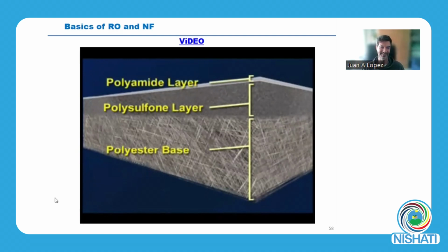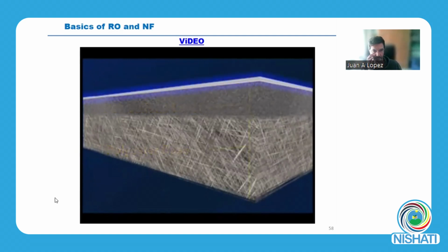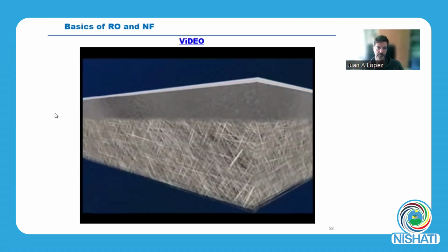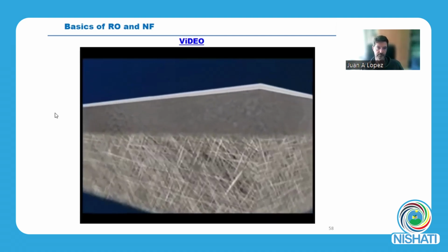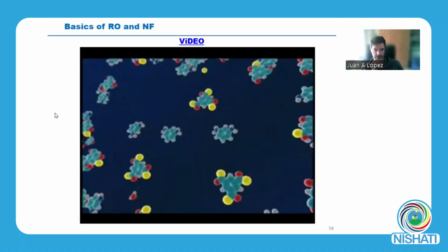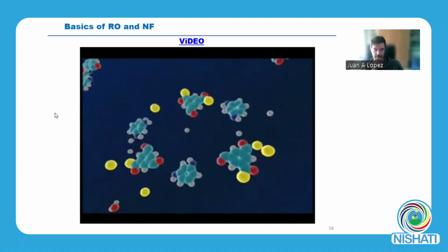Base and then coat it with a microporous polysulfone layer. This provides additional support for the top 0.2 micron thick membrane barrier layer. This top barrier layer makes the actual separation to purify the water. The semi-permeable polyamide layer consists of a thin film of polymeric material a few thousand angstroms thick, formed on a porous supporting material.